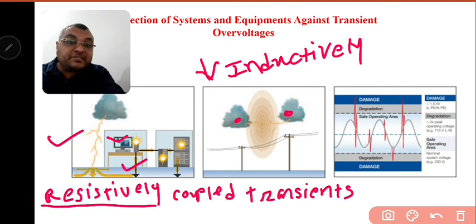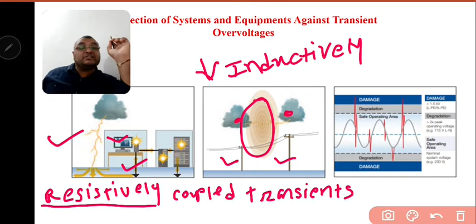A lightning discharge gives rise to an electromagnetic field - say, a lightning discharge happens between two clouds. If metallic services such as overhead power lines pass through this field, a voltage will be picked up or induced onto the line. If a metallic line comes into the path of that lightning discharge, the potential rises, and this is known as the inductively coupled transient.